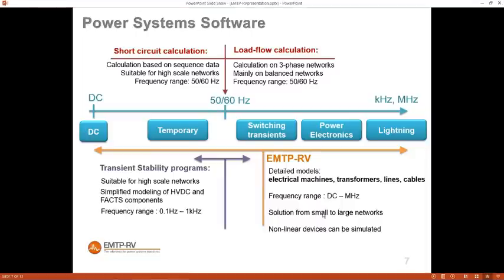Here are the frequency ranges we can study with EMTP-RV — essentially all frequencies present in the network. For high frequencies like lightning or switching transients, the parameters of the line and cable change: because of the skin effect, the resistance value increases and the inductance value also changes with frequency. In EMTP-RV we have frequency-dependent line models to reproduce this; the parameters change during the time domain simulation as a function of frequency. These are very powerful models.